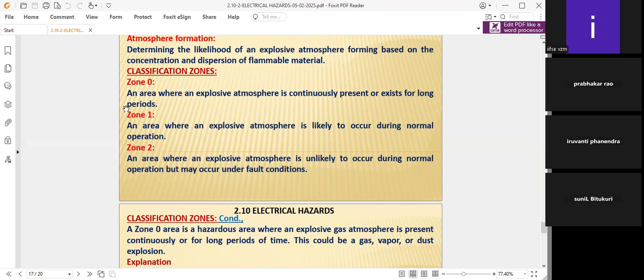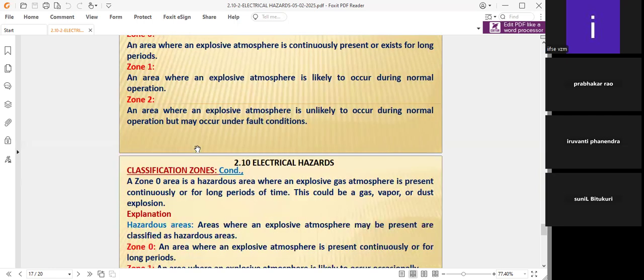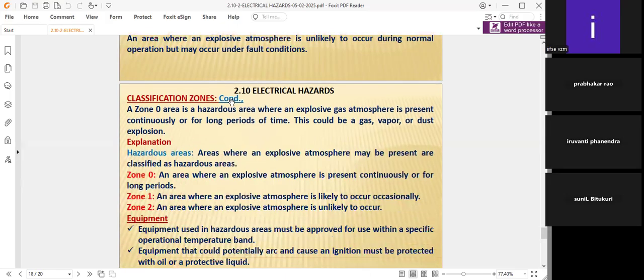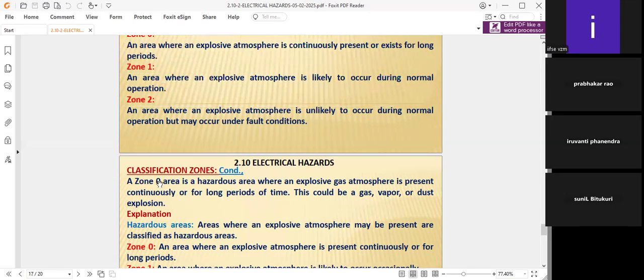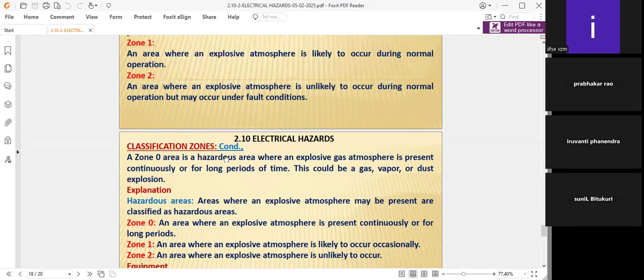These are the very, very important classification zones, and the classification of zones continues. A zone 0 area is a hazardous area. Again, I am repeating: a zone 0 area is a hazardous area where an explosive gas atmosphere is present continuously or for a long period of time. This could be gas, vapor, or dust explosions.